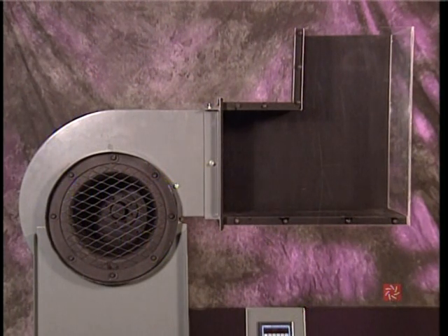When space constraints do not allow for a section of straight duct, an elbow must be placed near the fan outlet. But look what happens. This installation results in an abrupt change in direction of airflow. It causes turbulence within the fitting. One bad connection can reduce airflow significantly below the fan's catalog performance.